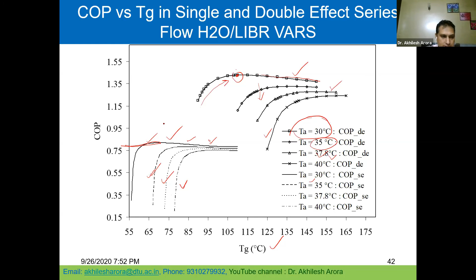Now this also shows the effect of the condenser as well as the absorber temperature. I would like to show which is causing more harm to the COP values. So you can see the upper graph here only. This is the curve when I am varying the temperature of the condenser between 30 to 40, and I have considered the absorber temperature as 30. For the varying condenser temperature, this is the curve for the COP. So it is reducing as the condenser temperature is increasing from 30 to 40.